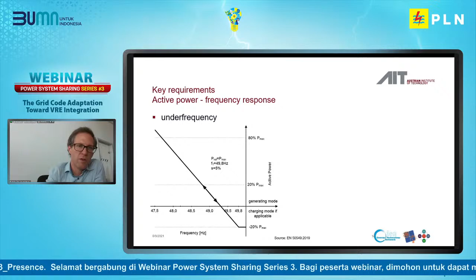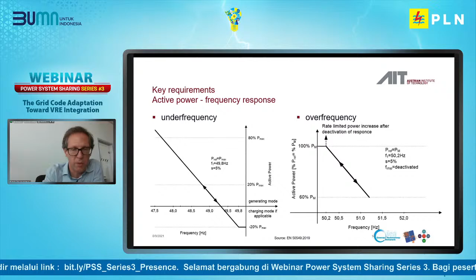Some more key requirements from the European perspective: first of all, the frequency response, for under-frequency as well as over-frequency. There are specific requirements depending on the size and the relevance of the generator. But all generation, even very small-scale residential generation, has to provide frequency support in the over-frequency range. This means that when there is an over-frequency situation, with frequency outside the normal operating bands, these generators have to reduce their power feed-in. For larger generators, there is also a requirement to actively increase power output in an under-frequency condition.